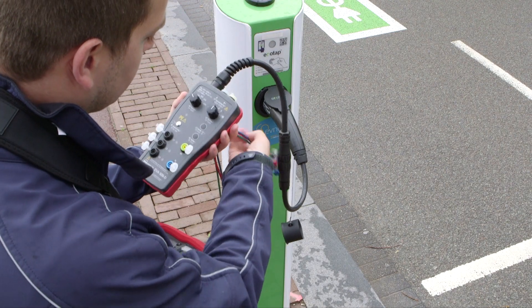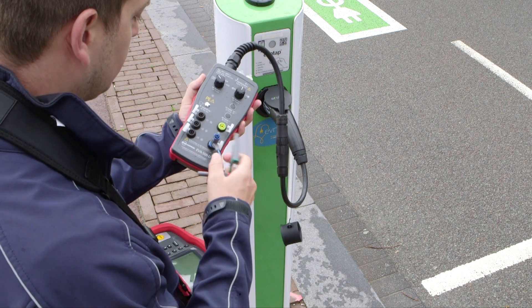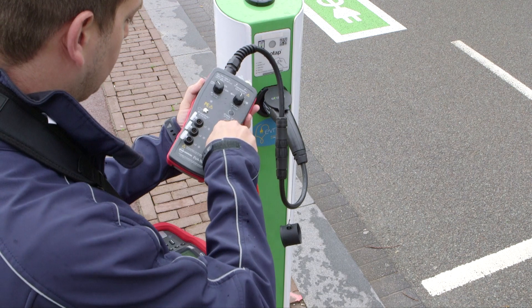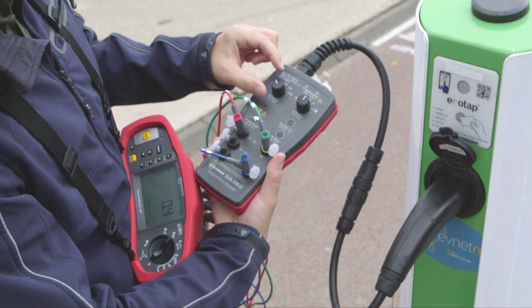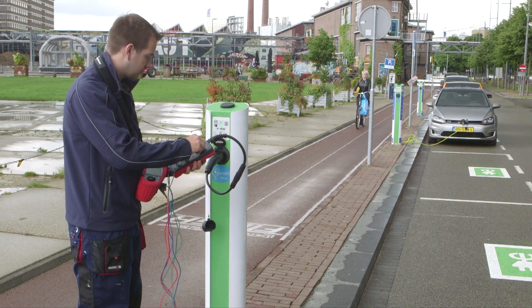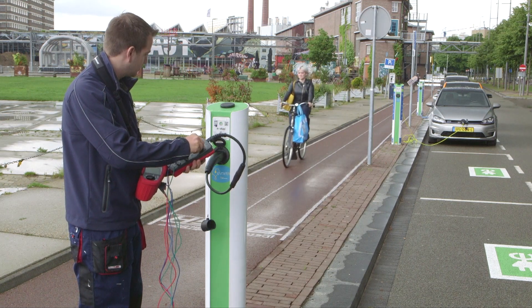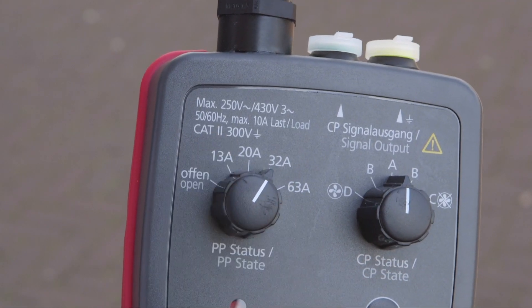After plugging into the charging station, connect your installation tester — typically a ProInstall 200 from Beha-Amprobe. Insert the live, neutral and earth connectors into the adapter. Use the proximity pilot status selector to set the appropriate current carrying capacity of the cable. In most cases, this will involve turning the switch to the 32 amp position.